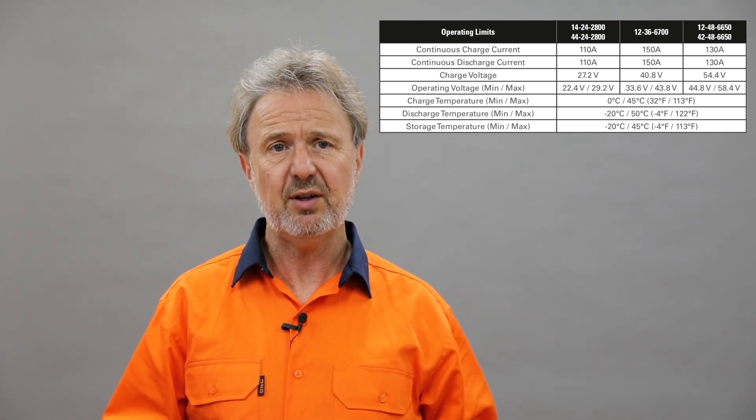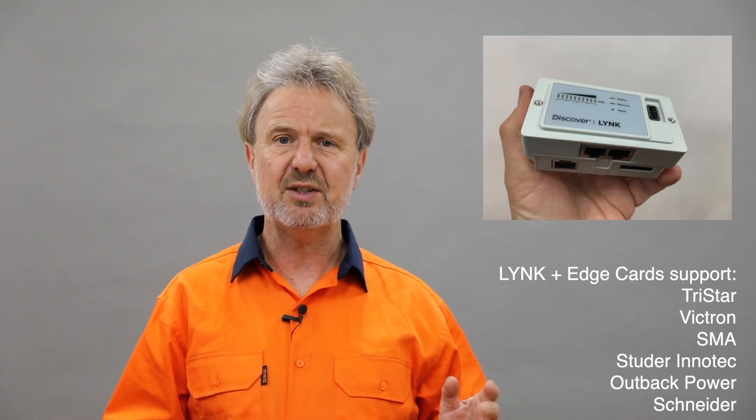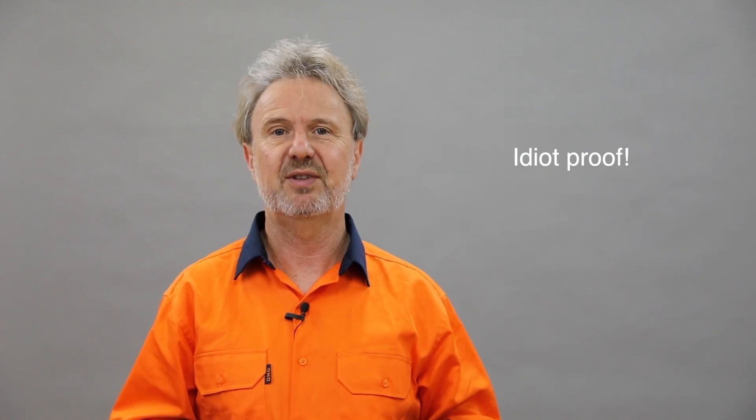The Discover AES battery has very close integration with the Schneider XW Plus inverter via Xanbus, the communication system Schneider uses. When you plug the comms cable between the Discover battery and the Schneider system, it straight away pushes the configuration through to the Schneider charging sources. I didn't realise it did this — I was trying to reprogram the charge controller and just couldn't change the settings. I contacted Discover and they explained that it pushes the correct settings through and you can't change them, because it wouldn't be safe. So it's got inherent safety — the fact that it pushes those settings straight through.